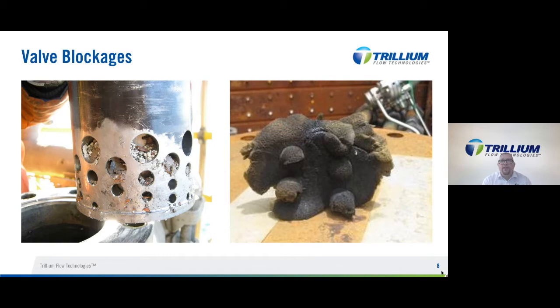When they opened the valve, they found that the internal lining of the valve had completely peeled off and the debris had blocked the valve. In the picture on the right, we see another common reason for blockages. Everyone who deals with valve applications will be familiar with the rag, the sponge, the welding and other debris in the valve. In more common control and choke applications, there is at least some filtering of the sand, and usually the sand is more a fine talcum powder than large particles, but this again still causes problems.